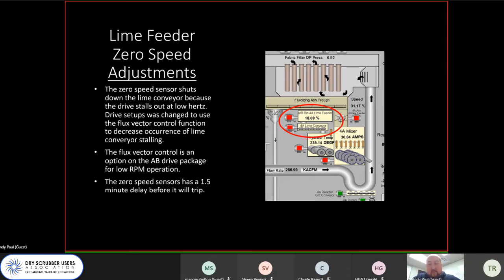Now, I'm an operations guy, I'm not an electrician guy, so I'll do my best. But we installed this flux vector control, and essentially it allowed us to run the drives down to a very low speed and prevent them from stalling out when we had very low hertz on the drive. We have a minute and a half delay before the feeder trips. When we have excessive feeder trips, operators wind up just biasing up the feed rate so that they don't have to continuously reset the feeder, and therefore we go through more lime than we need to.